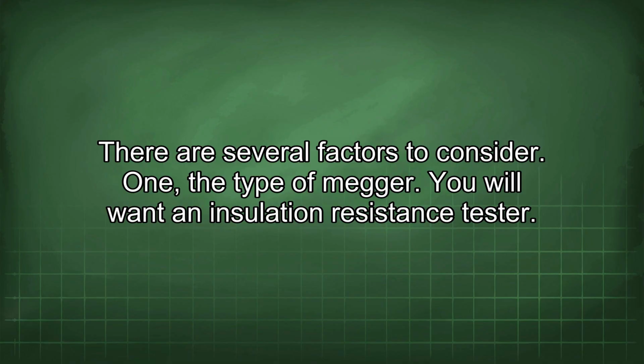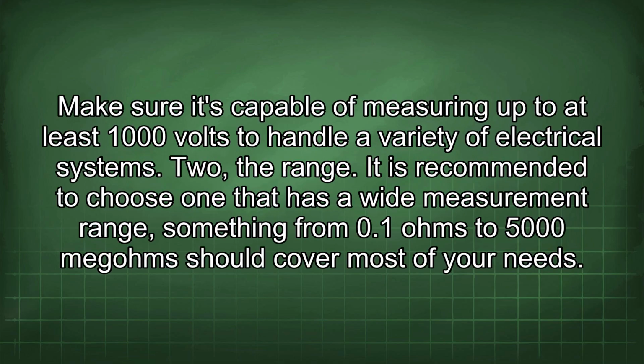1. The type of Megger. You will want an insulation resistance tester. Make sure it's capable of measuring up to at least 1000 volts to handle a variety of electrical systems. 2. The range. It is recommended to choose one that has a wide measurement range. Something from 0.10 ohms to 5000 megohms should cover most of your needs.